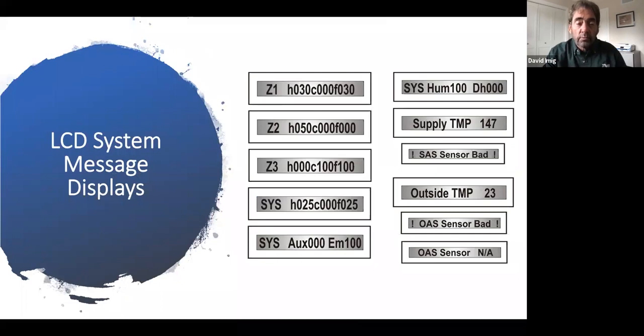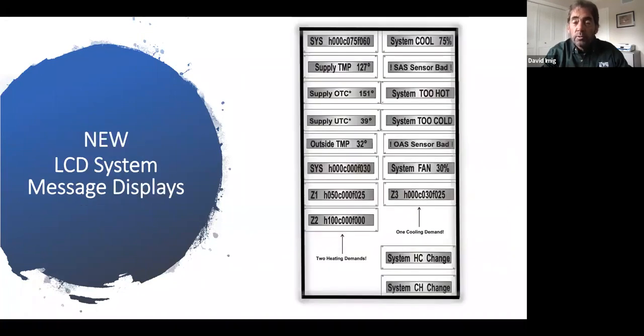Some of the readouts that you get from this are just that. They're readouts telling you what's going on and if it's going on and what's going on in each of the zones with the system demand, with any auxiliary, with any IEQ products. Most importantly, it tells you on the fly supply temperature so that you can monitor that and see if the equipment is operating properly based on the supply temperature and so on. Some new things that were added is just more information that will tell you in an LCD scrolling message what's going on at any given time.